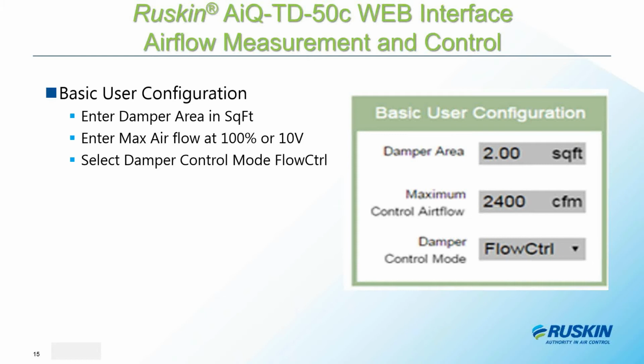So it's pretty straightforward. What we've done at the factory is we've wired sensor input 1 to the airflow output from the TD-50C. So what's coming in on sensor input 1 is the airflow measurement. And the next step is to configure the device for the maximum airflow expected. The factory default, if left unchanged, will be 5,000 feet a minute. That means that at 100% output from the TD-50C, you'd get 5,000 times 2, or 10,000 CFM in this case.